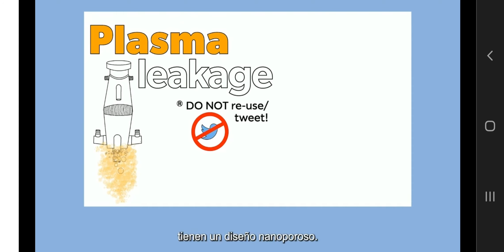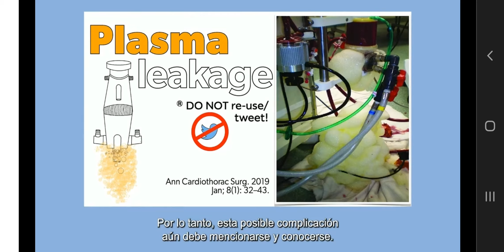The risk of plasma leakage with previous generation polypropylene hollow fibers, which have a microporous design, is consistent. Consider that polypropylene membrane lungs are still used in local circuits used in short-time ECLS, as procedural ECMO or EISOR, extracorporeal interval support for organ retrieval in DCD donors. These circuits are also used sometimes for ECPR, at least at initiation, and during COVID-19 have been used in constrained resource settings due to the lack of long-term circuits. So this potential complication still needs to be known and mentioned.